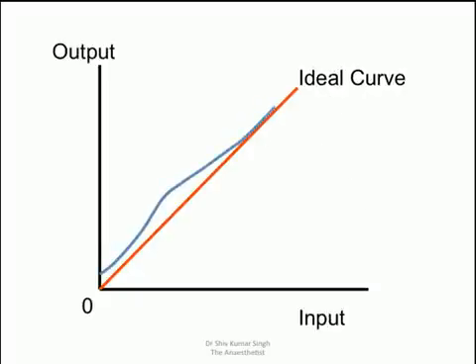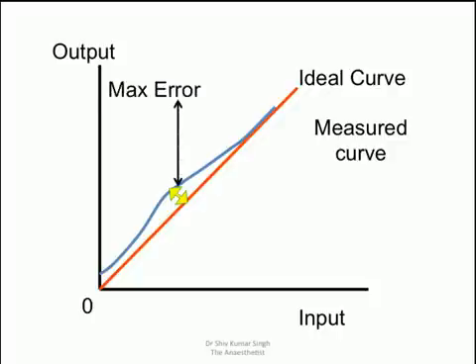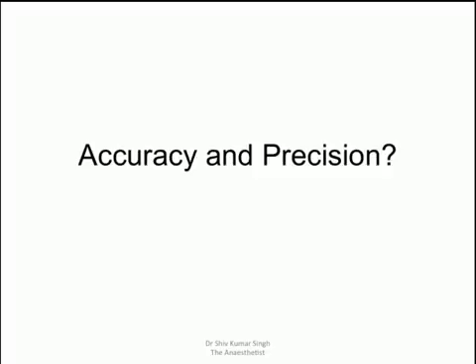But that is never true in real life. In real life the curve looks like that. The measured curve in blue. So if you look at this curve there are huge errors at the lower values, whereas it's very linear at the upper part. So this instrument will be fine to be used at higher values. The higher values can be trusted but not the values at the lower end where there can be huge errors.